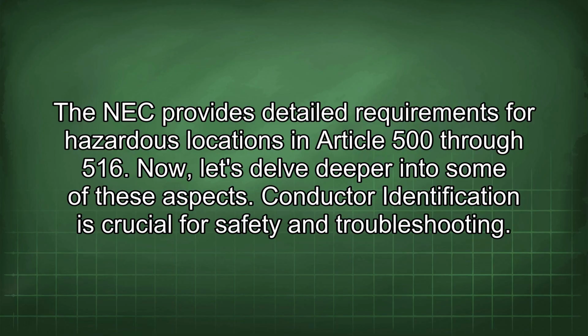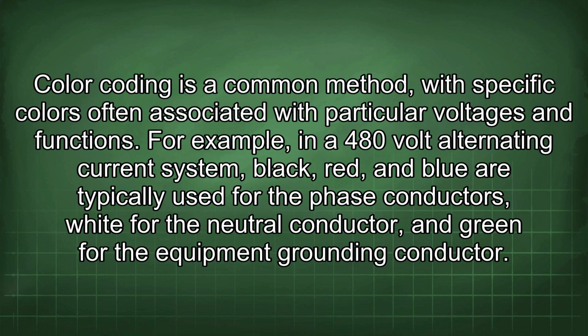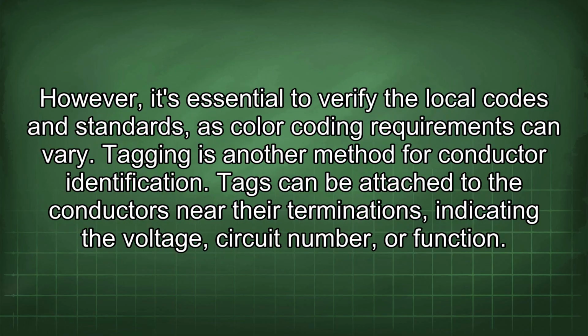Now let's delve deeper into some of these aspects. Conductor identification is crucial for safety and troubleshooting. Color coding is a common method, with specific colors often associated with particular voltages and functions. For example, in a 480-volt alternating current system, black, red, and blue are typically used for the phase conductors, white for the neutral conductor, and green for the equipment grounding conductor. However, it's essential to verify the local codes and standards, as color coding requirements can vary.